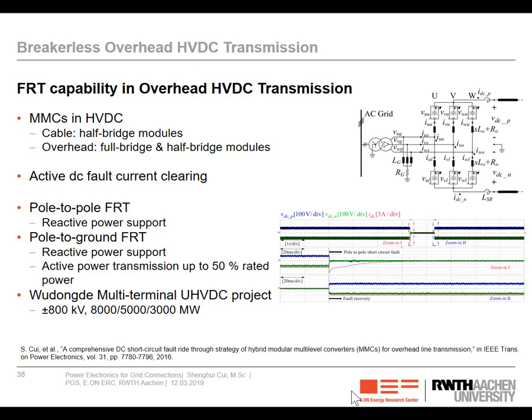But here, if we have such a mixture, then it's possible to control the AC side current. In the meantime, the DC voltage can be either VDC or zero or minus VDC. Then, as long as a short circuit fault occurs, we can immediately decrease the DC link voltage from VDC to zero.